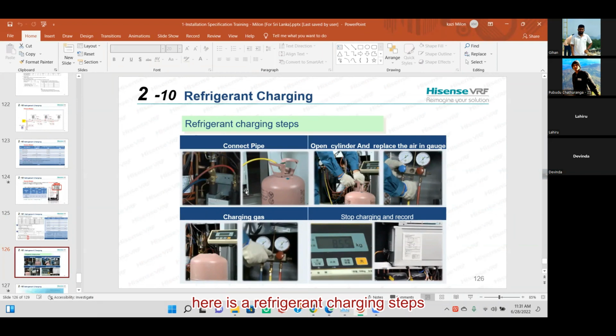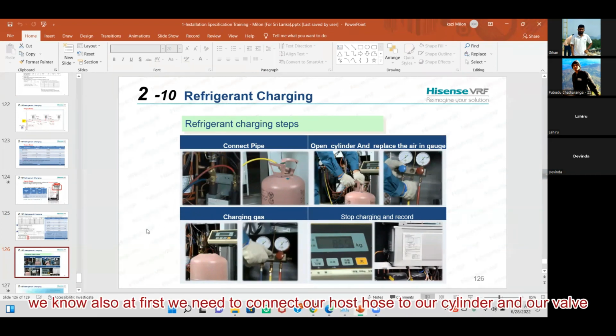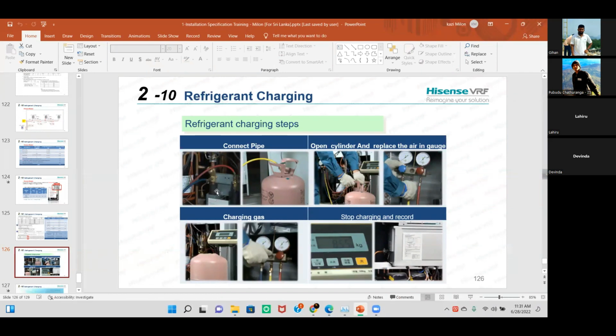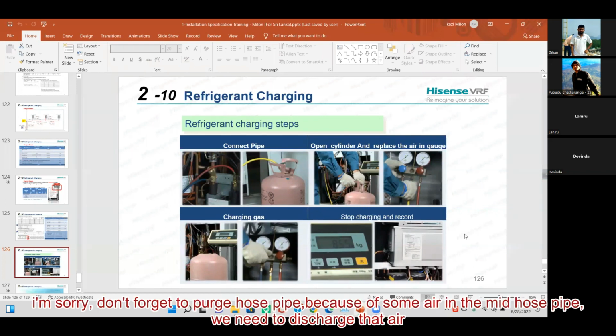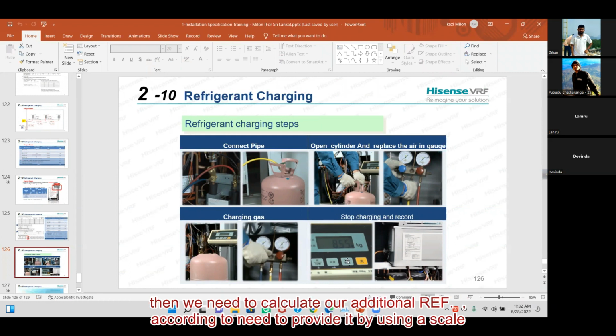Here are the refrigerant charging steps. At first we need to connect our hose to our cylinder and our valve, and don't forget the purging. Don't forget to purge the hose pipe, because there is some air in the hose pipe, we need to discharge the air. Then we need to calculate our additional refrigerant, and according to the need, provide it by using a scale. So it's okay.